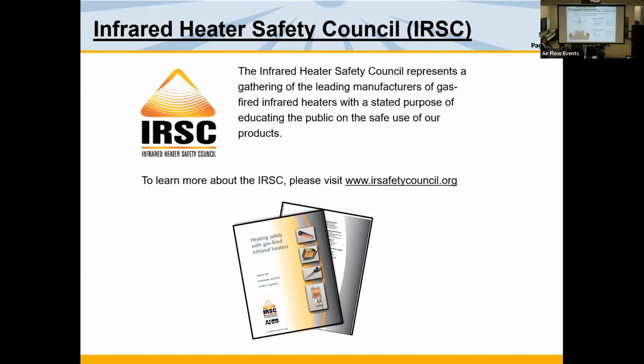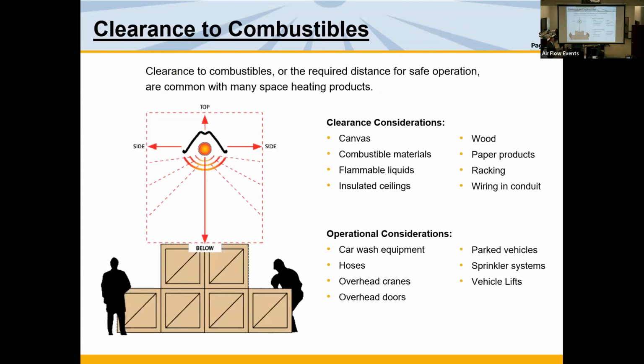Next slide. You need to understand clearance to combustibles. Now, unlike our minimum mounting height, clearance to combustibles is the distance that we must keep a combustible item away from the heater. That's mandatory. If we keep that distance, we won't have problems. So every heater has a top clearance, a side clearance, and a bottom clearance. And what we're paying attention to is canvas awnings. We're looking at cranes. We're looking at racking. You know, in that lumber yard, are they storing lumber too high to a heater? There's a lot of things that go into that. But the clearances are mandatory.